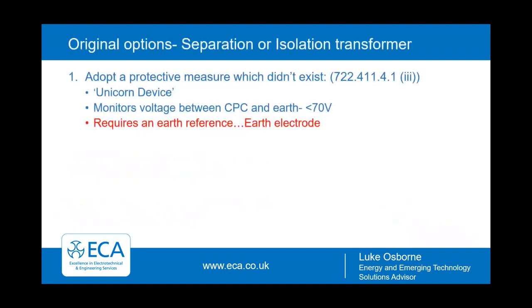So there were existing options available to the electrical contractor for installing electric vehicle charging equipment. The first was the adoption of a protective measure which didn't currently exist. This was in Indent 3 of 722.411.4.1. This was the fabled unicorn device, often sought, never found. It operates by monitoring the voltage between the CPC and earth and activating if that exceeded 70 volts. It does require an earth reference electrode in order to take these readings.